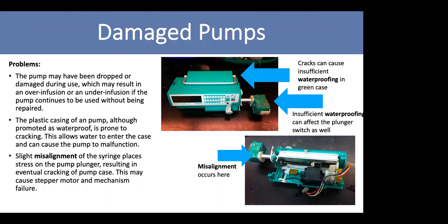So when you talk about damaged pumps, these are normally what a biomed is going to look into. Very common issue. The main reason is the syringe or infusion pump itself has been dropped so many times or heavily dropped. Eventually you get cracking on the casing, and the waterproofing is not working properly anymore, so you end up getting fluid going inside.